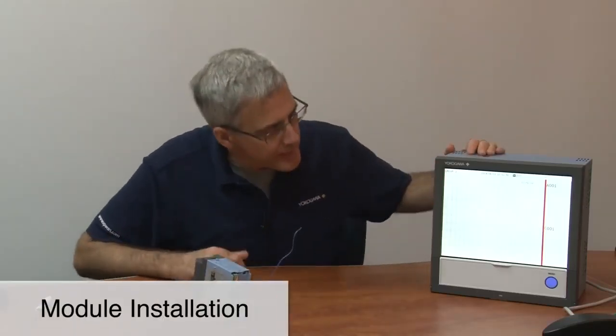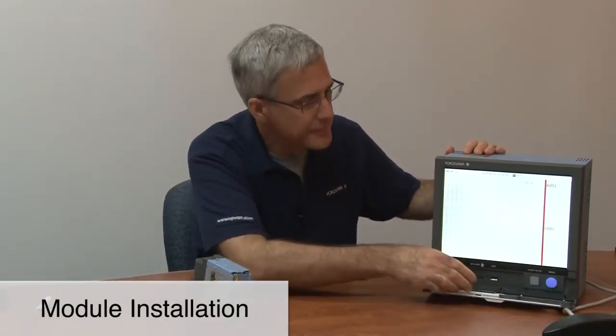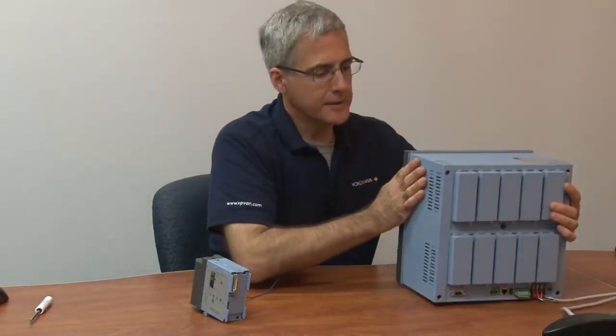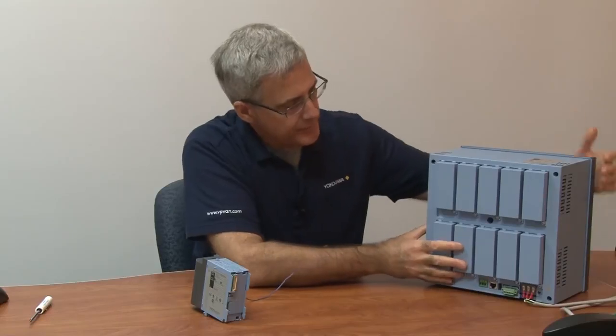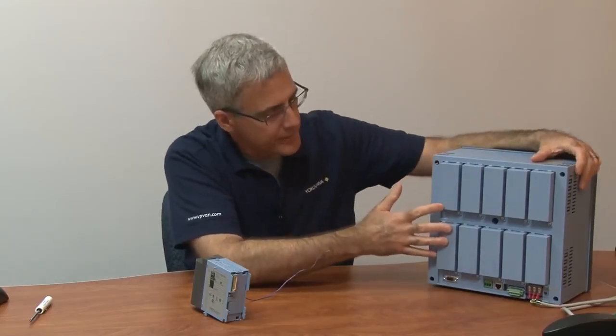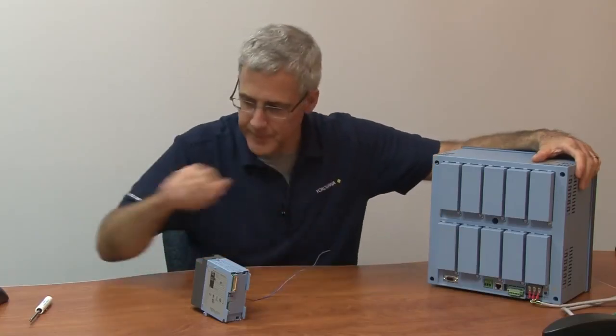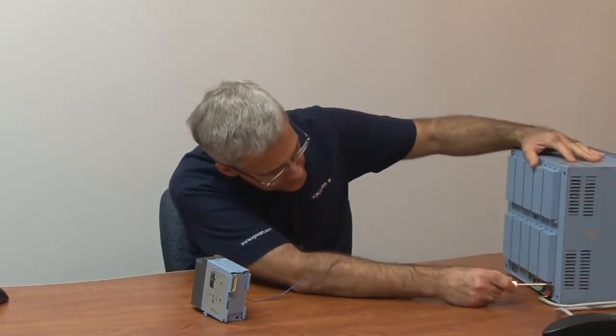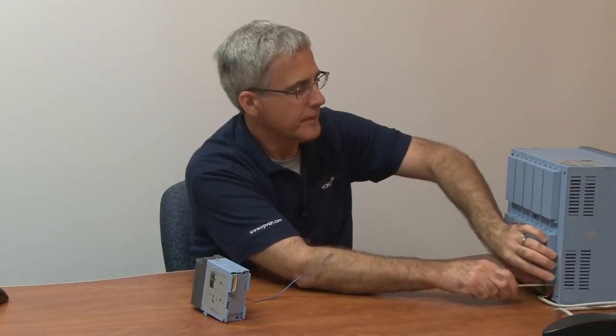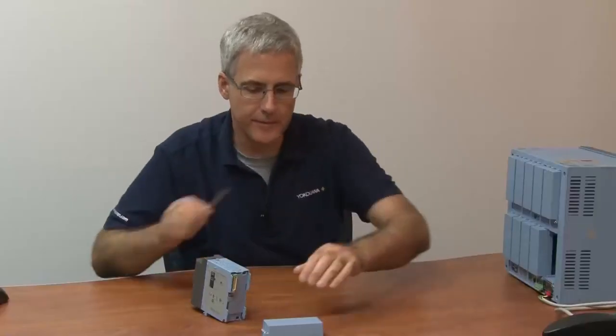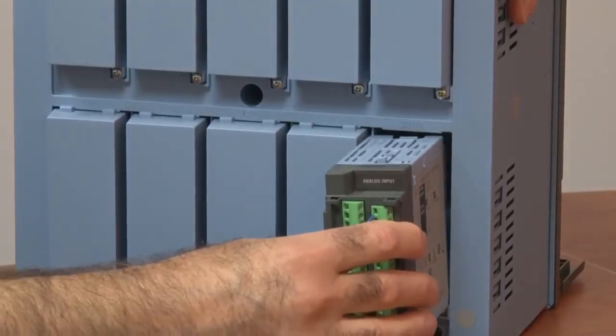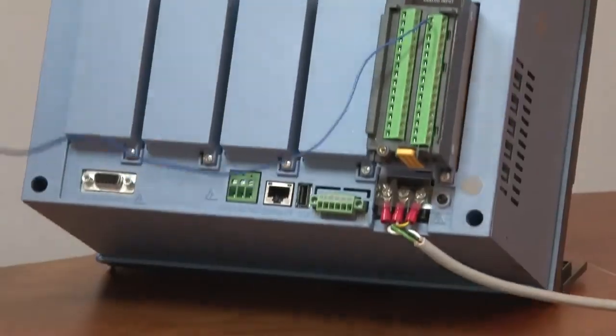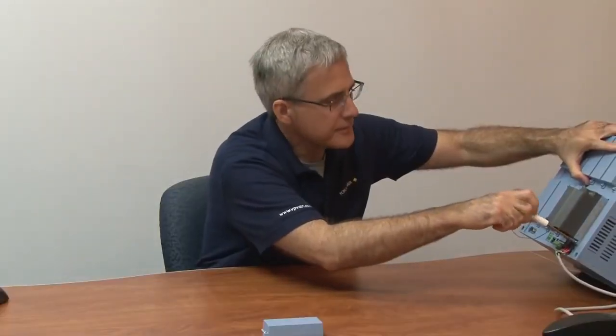So the first thing is we're going to turn the power off. We always want to attach the modules with the power turned off. Have a look at the rear panel. And on the GX20, we have 10 module slots. The slots are numbered 0 through 9. So the first thing we're going to do is undo the terminal cover for slot 0, and pop our module in. Just take the cover off. Module slides in. It'll snap right into place. And we just cinch down the retainer screw, and we're good to go.